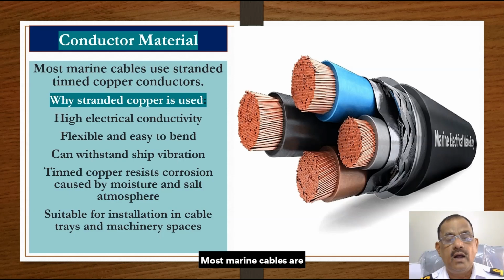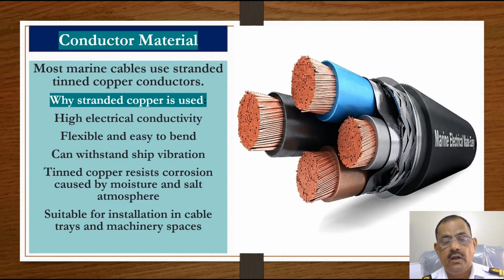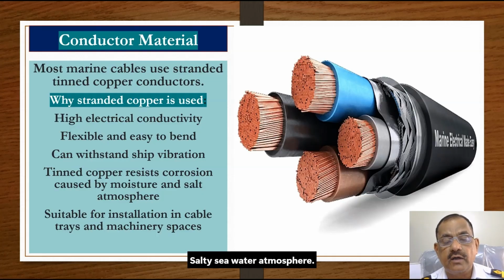Most marine cables are stranded tinned copper conductors. Copper is used because it has very good electrical conductivity. This means it can carry current efficiently with less resistance. The conductor is made of many small copper strands instead of one solid conductor, and it can also withstand vibration, which is very common on ships due to engines, pumps, compressors and ship movement. The copper is tinned to protect it from corrosion caused by moisture and the salty seawater atmosphere.